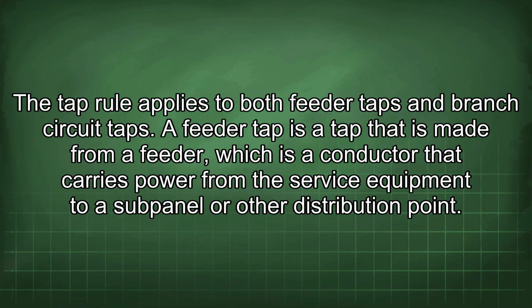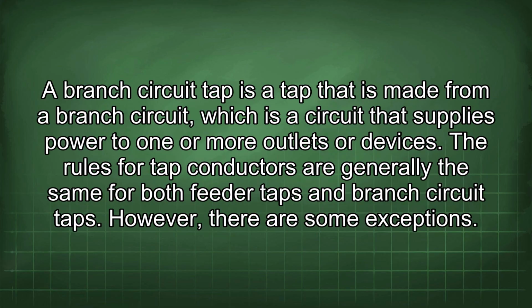The tap rule applies to both feeder taps and branch circuit taps. A feeder tap is a tap that is made from a feeder, which is a conductor that carries power from the service equipment to a subpanel or other distribution point. The branch circuit tap is a tap that is made from a branch circuit, which is a circuit that supplies power to one or more outlets or devices. The rules for tap conductors are generally the same for both feeder taps and branch circuit taps. However, there are some exceptions.